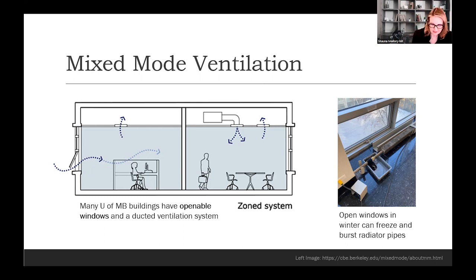Mixed mode systems generally operate seasonally. They work in the fall and they work in the spring because the windows are open for something called free cooling. We can get free air conditioning if we open the window. So a lot of the buildings were designed this way so that you don't have to condition the air in the shoulder seasons, the fall and the spring. But in Winnipeg, the winter is so cold that the heating system is not able to adequately condition the rooms. So the temperature in the room can fall quite dramatically if you open the window. Similarly, in the summer, the air conditioning systems can't cool the air fast enough if you open a window, so the room can heat up pretty fast.